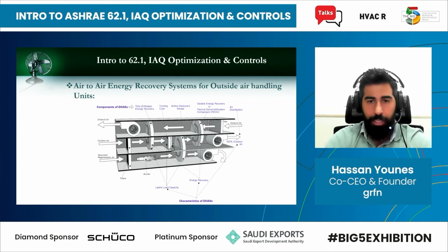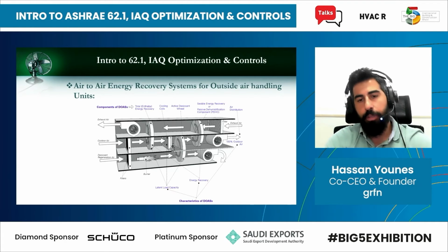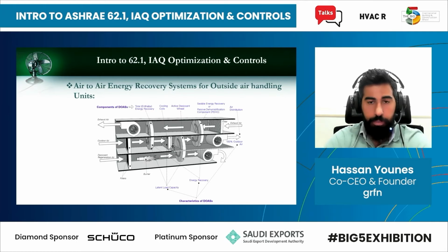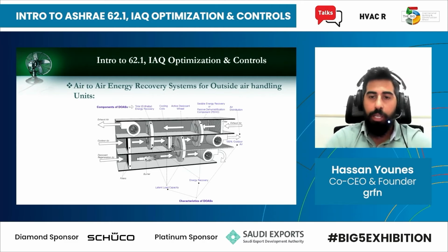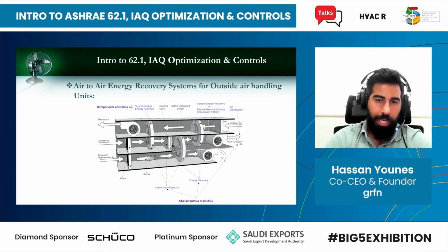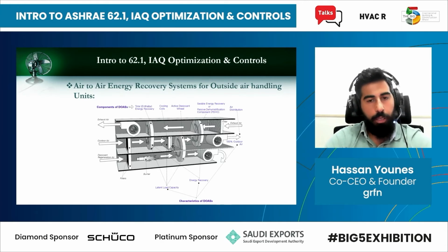This is a schematic showing two wheels, and there's also another wheel for a desiccant dehumidification system. So you can see there's one wheel, which is a total enthalpy wheel, and there's a sensible energy recovery wheel just after the cooling coil that will basically do a free reheat for the outside air, so you don't overcool the spaces. At the same time, it will cool down the exhaust further, so you have more and better dehumidification and cooling at the enthalpy wheel.